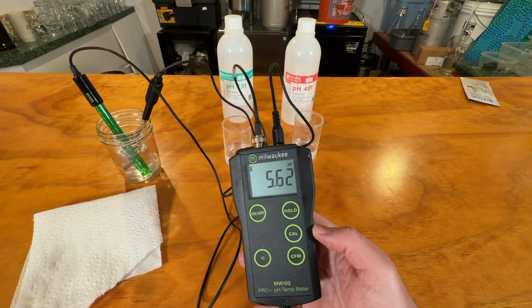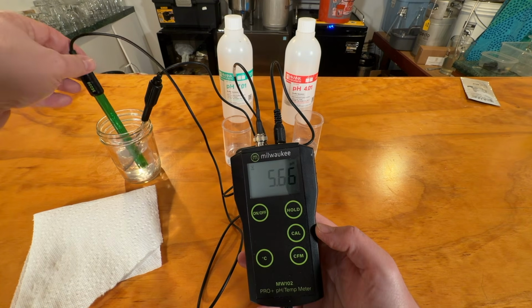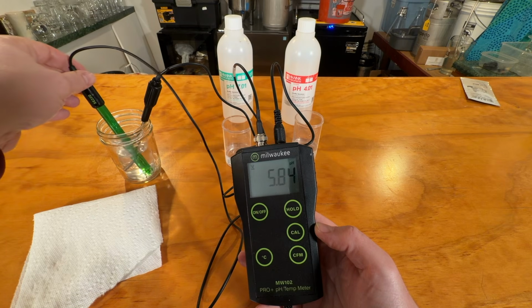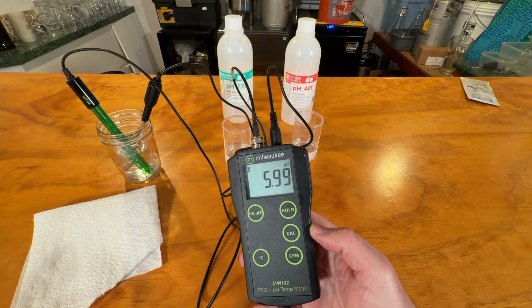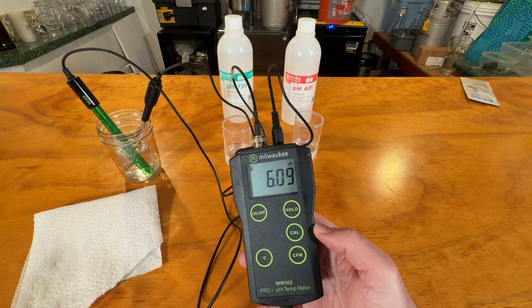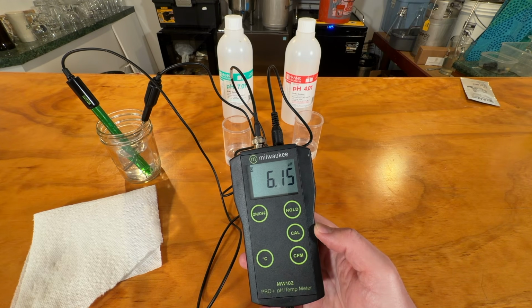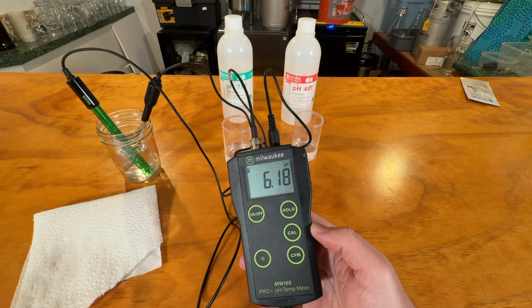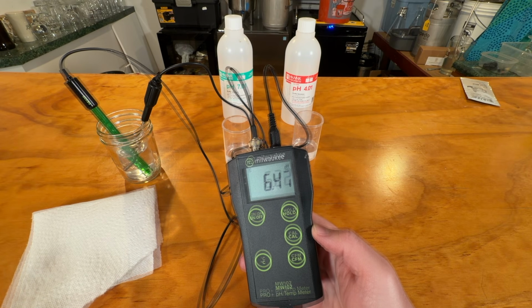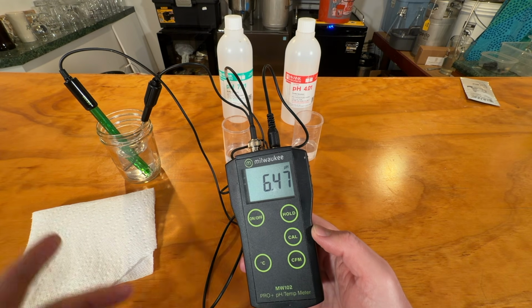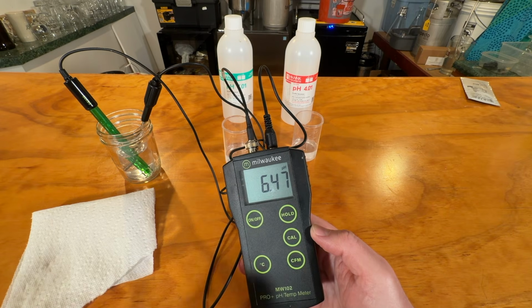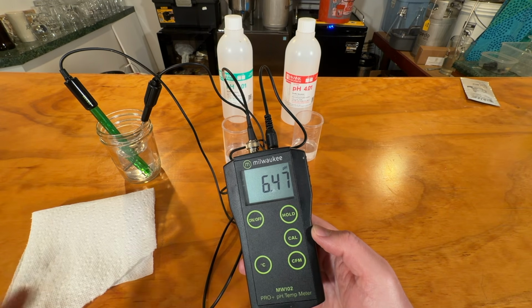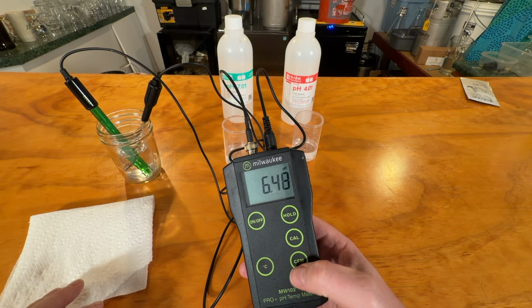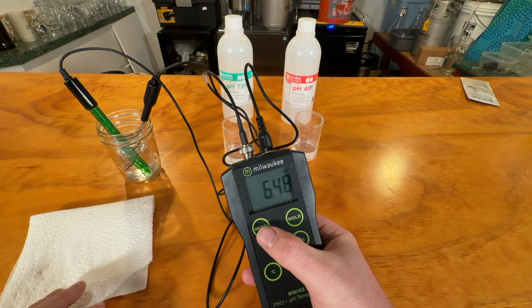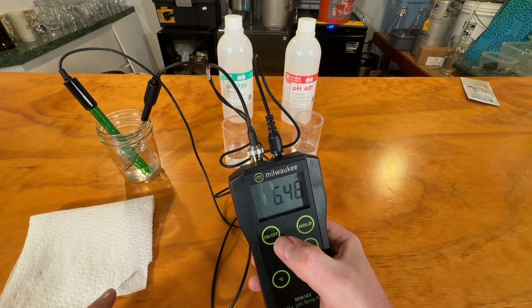And when it's done making a reading and it's stable, you can stir it a little bit. But that's how you make your first pH reading after doing your calibration. There you go. So once the little hourglass goes away, that's its stable reading. That's what it's reading there. So then I'll show you what to do with the probe when we're done. Let me move the cameras around.